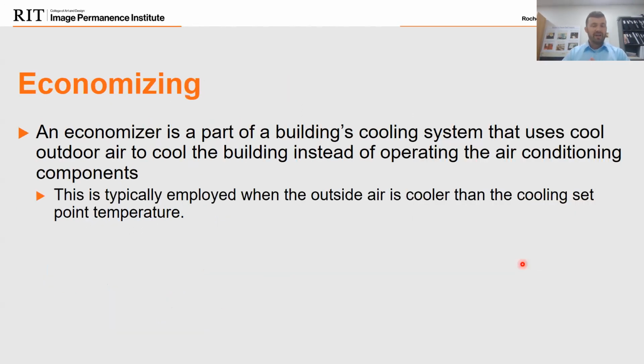And lastly, here we have the economizing. The economizer is a part of the building's cooling system that uses cool outdoor air instead of operating the air conditioning components. As an example, in that example I gave earlier, we were aiming for 70 degrees, 50% relative humidity, and just happenstance, say outside, those conditions were very close or a little cooler than what we wanted. Then they would bring in more outside air, or maybe even 100% outside air, as a source of cooling rather than running the cooling coils on the system, as a form of free cooling for the unit.